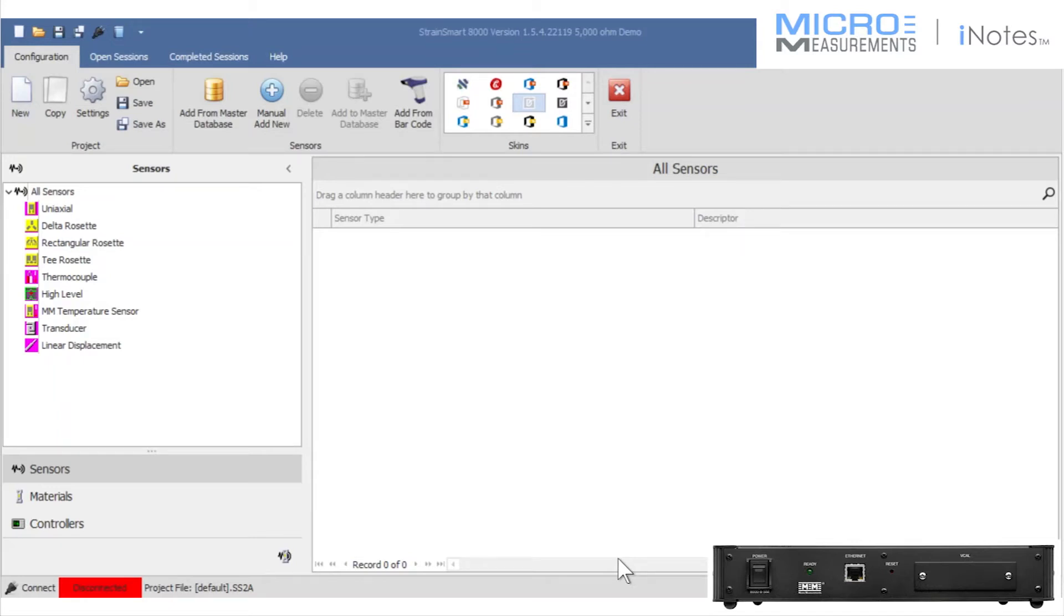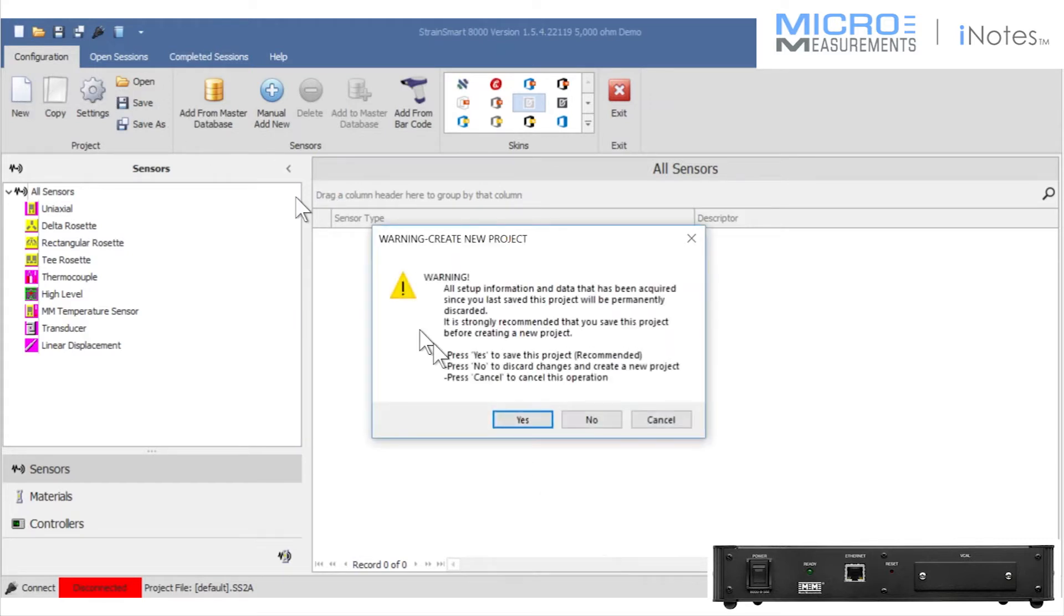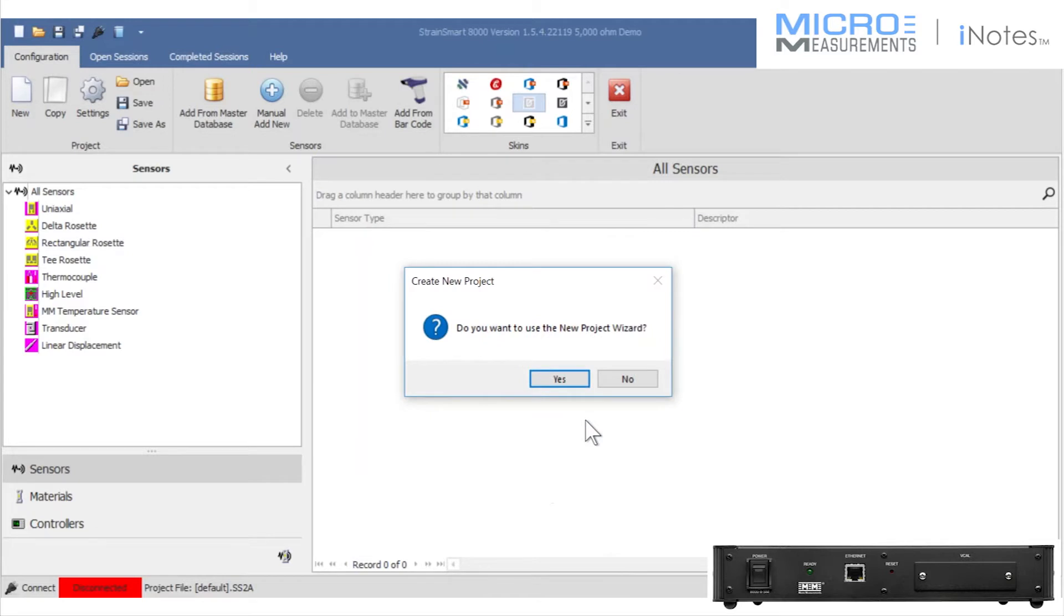Now that the System 8000 scanner is configured for a 5,000 ohm quarter bridge input, I need to go in and copy the project file. It's going to accommodate both it and the 350 ohm quarter bridge gauge. I'm going to utilize the project wizard.